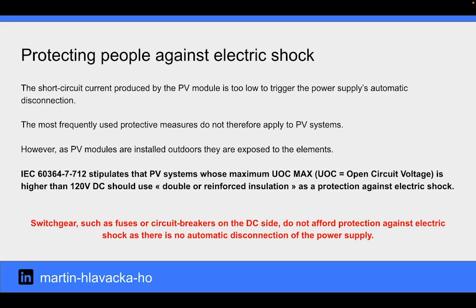The short circuit current produced by the PV module is too low to trigger the power supply's automatic disconnection. The most frequently used protective measures do not therefore apply to PV systems. However, as PV modules are installed outdoors, they are exposed to the elements.